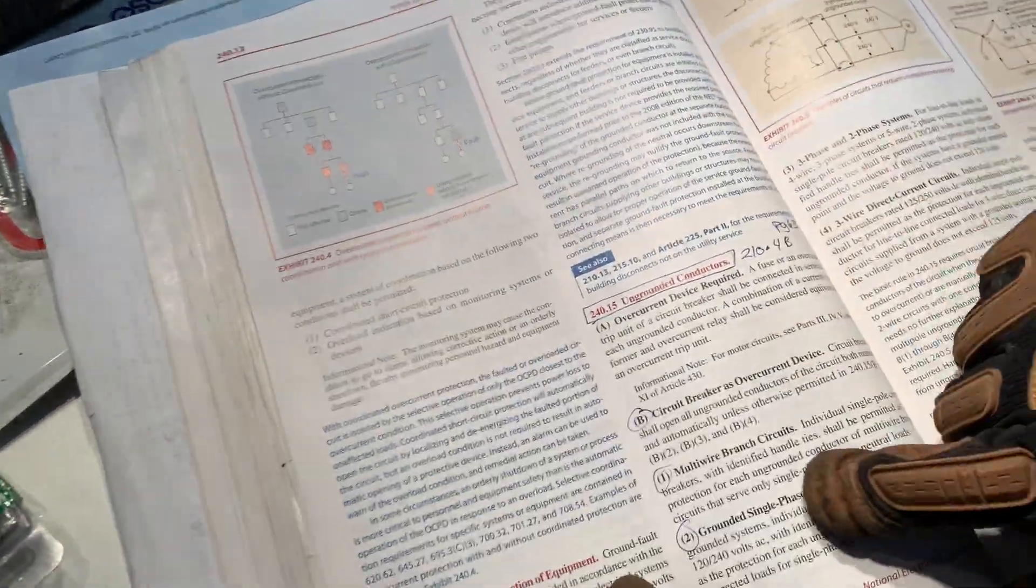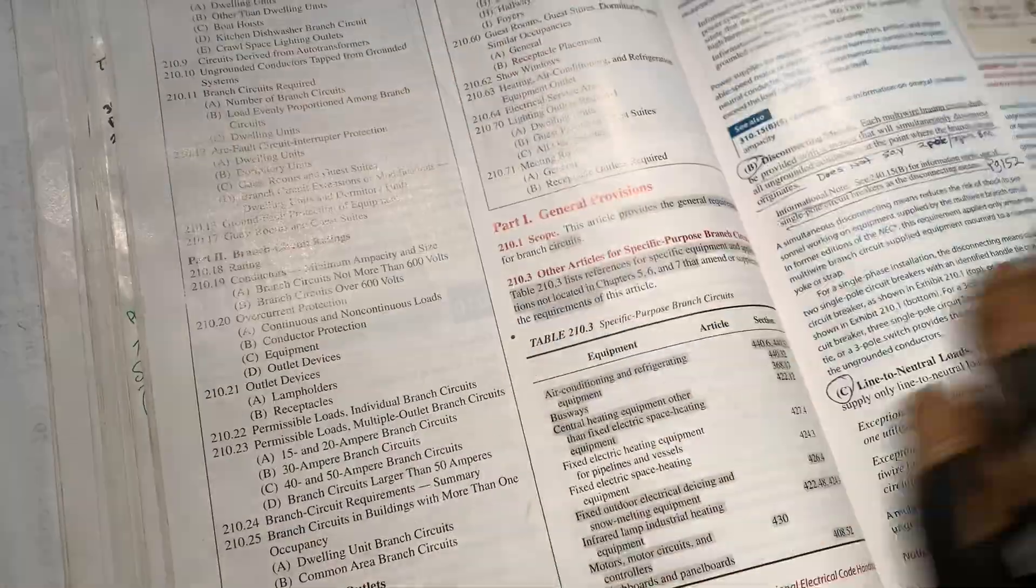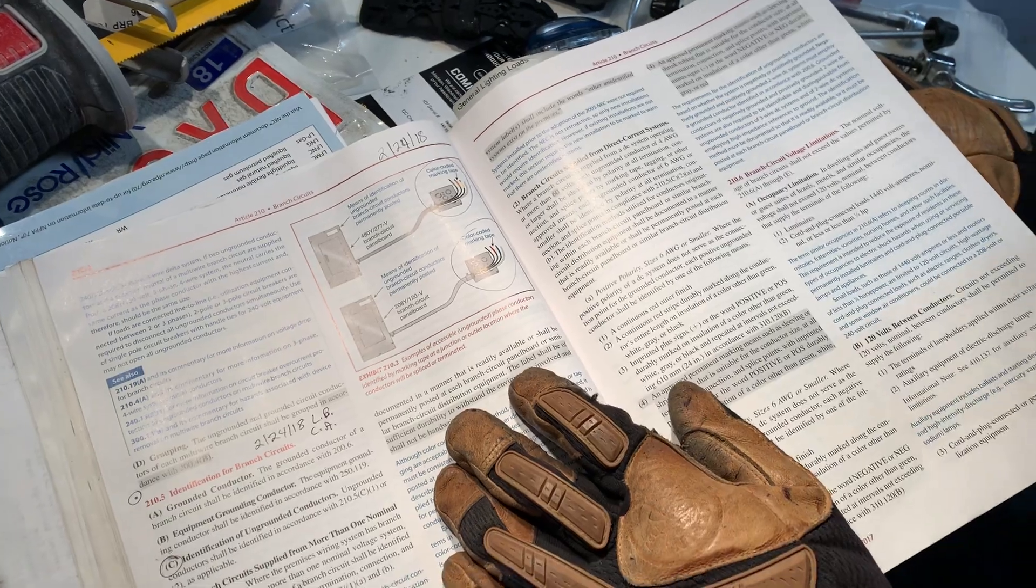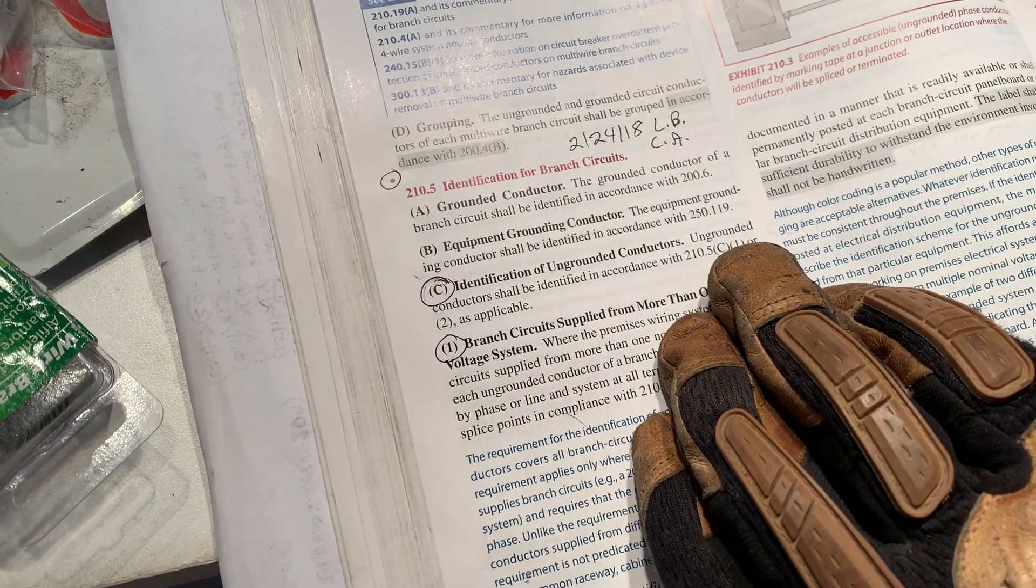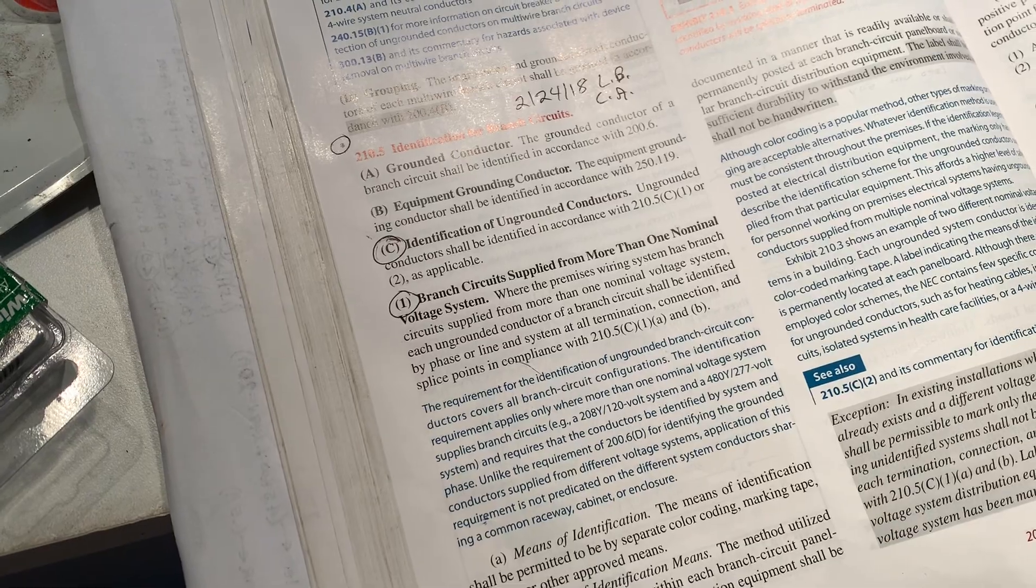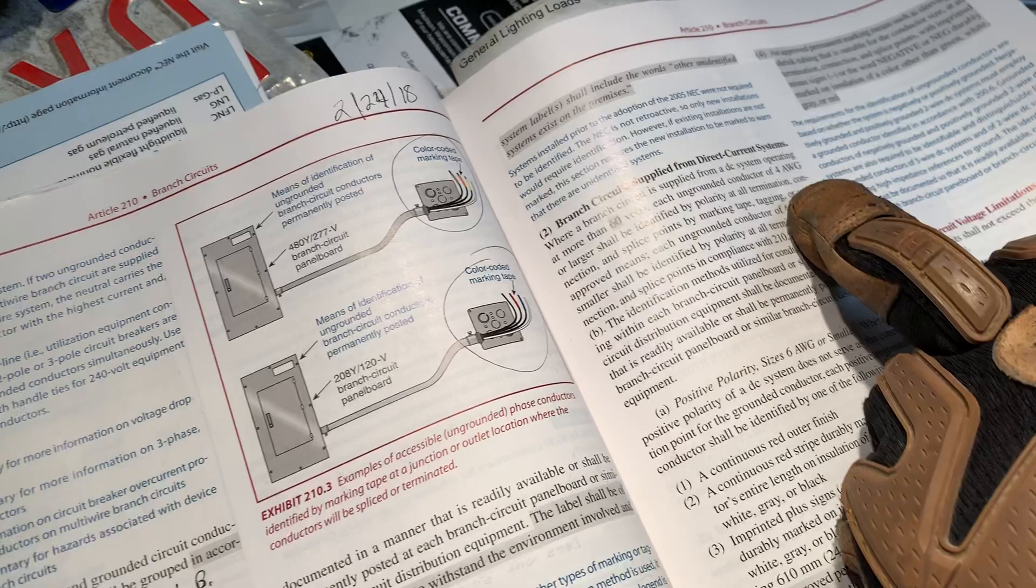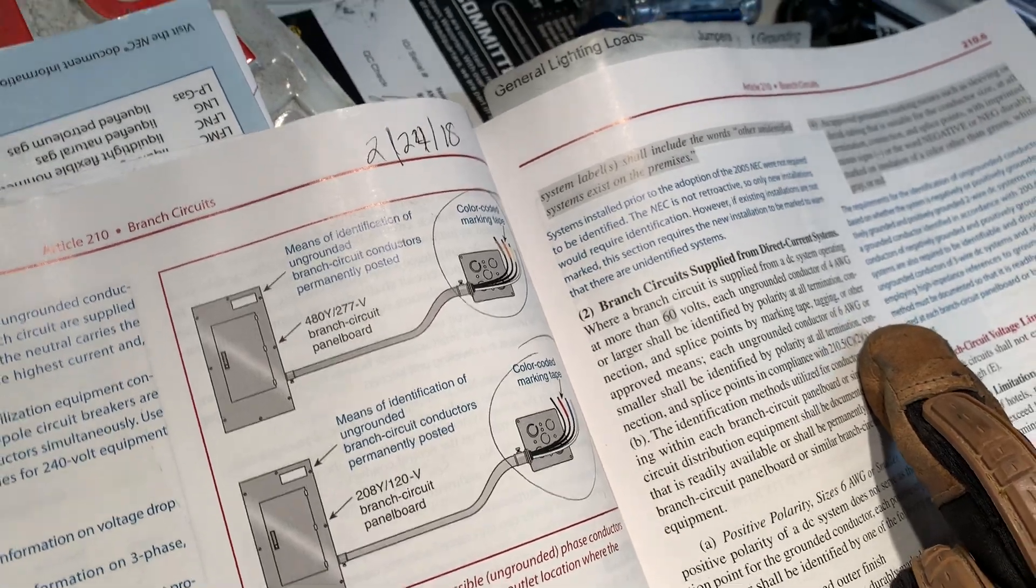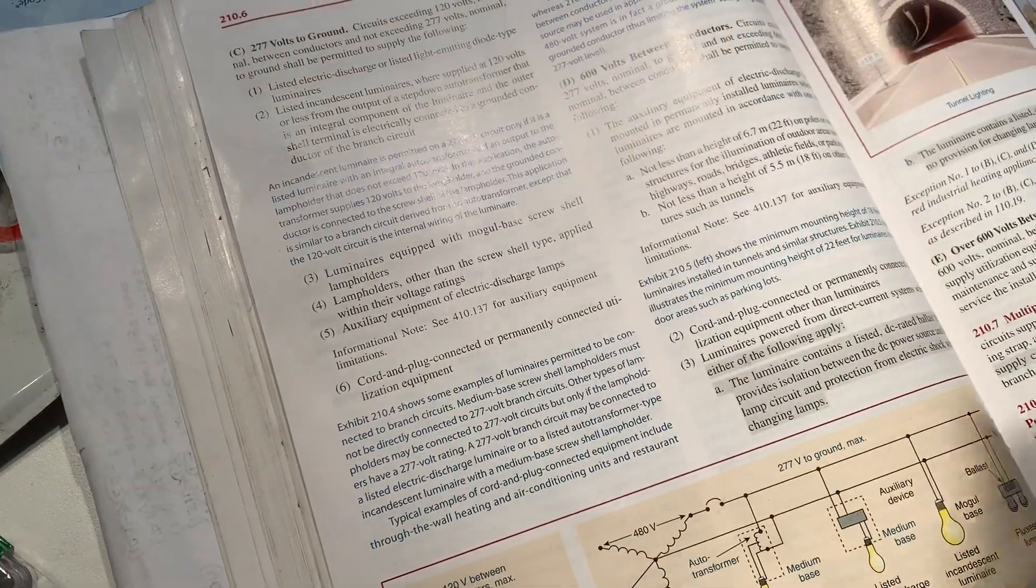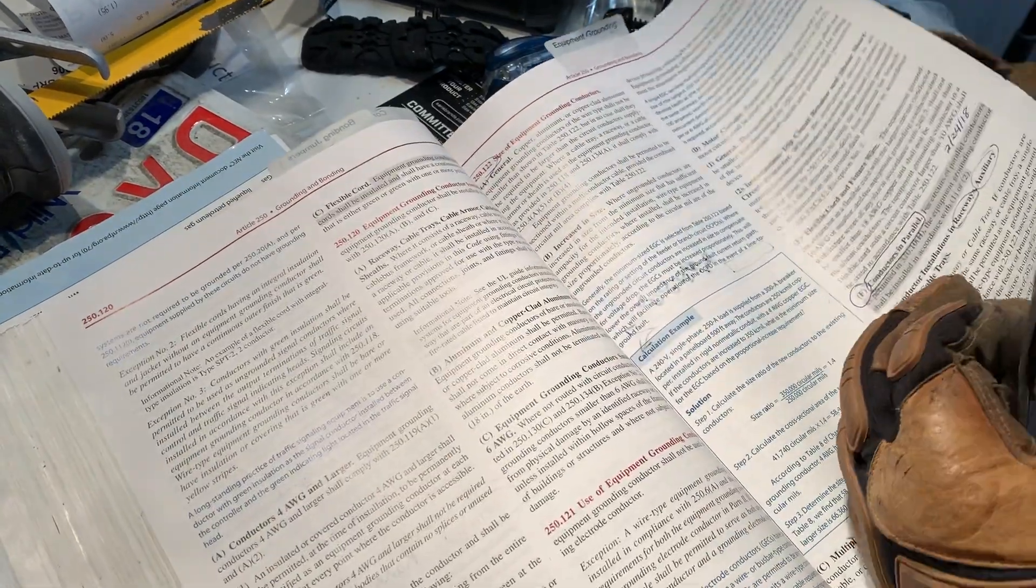The other thing that I did see, multi-circuit branch circuits, I believe it's talking about here. It's going to be 240.15. But we also want to look at the identification. They used a lot of different color wire, like white for black on grounded conductors. And they used then also a number 6. They had it all red. The code is pretty specific. Some inspectors give us grace if all we have is just black wire for number 6. But identification on ungrounded conductors, it talks about it in 210.5C as well. They talk about these voltages and any size wire. Branch circuit identification of each ungrounded conductor of 4 gauge or larger to be identified and terminated and tagged. But when you're dealing with smaller wires of 14, 12 gauge, 10 gauge, they typically want the whole conductor to be insulated in the same color.